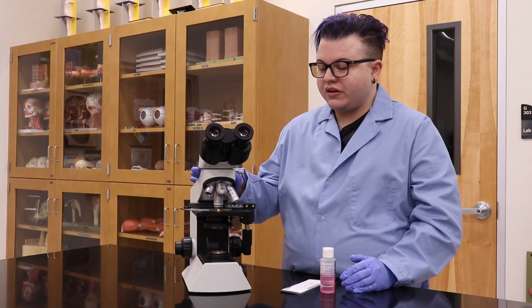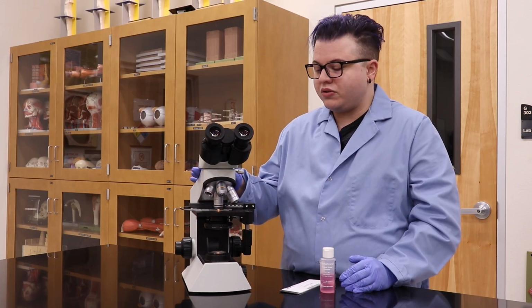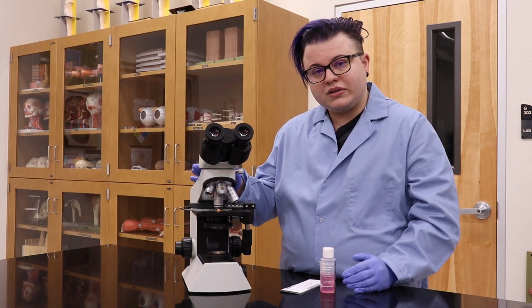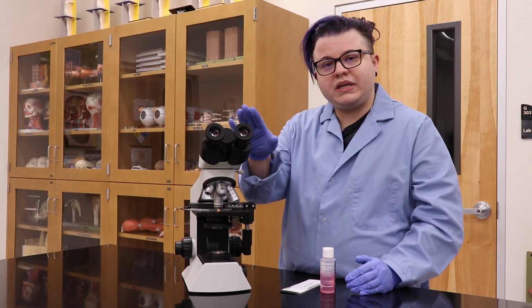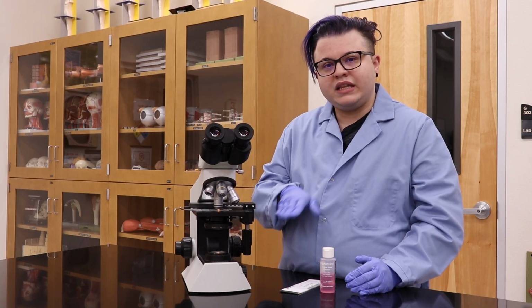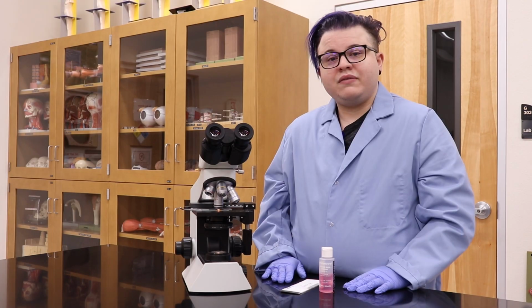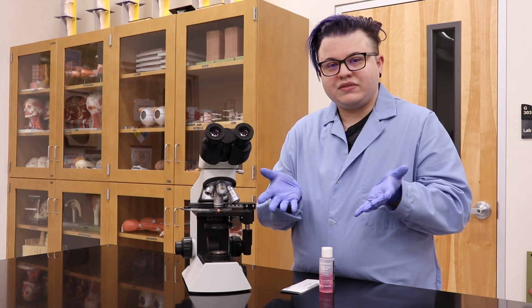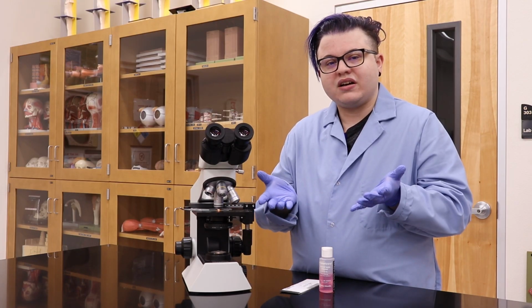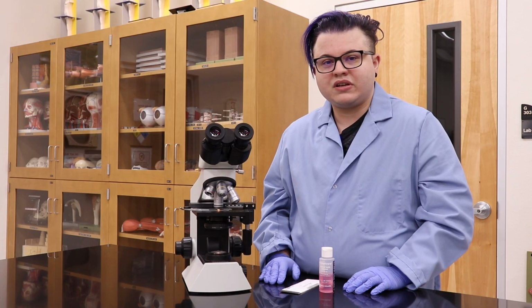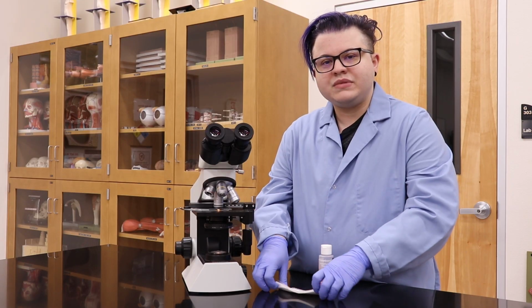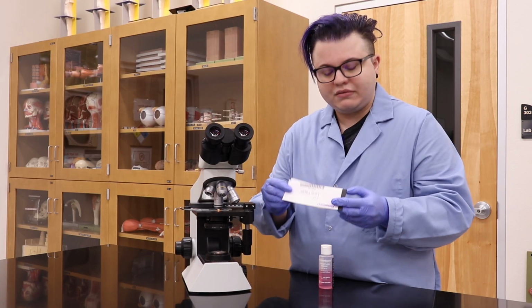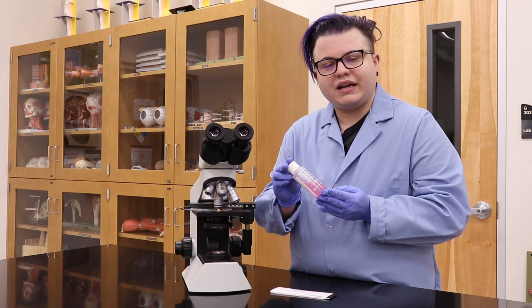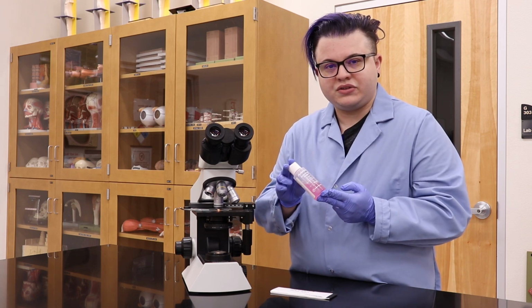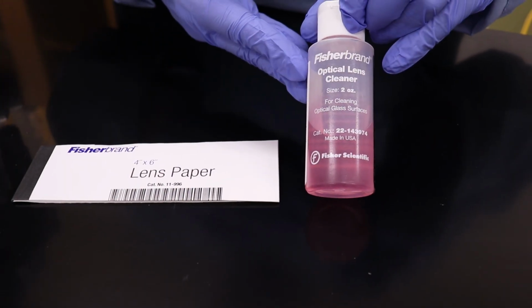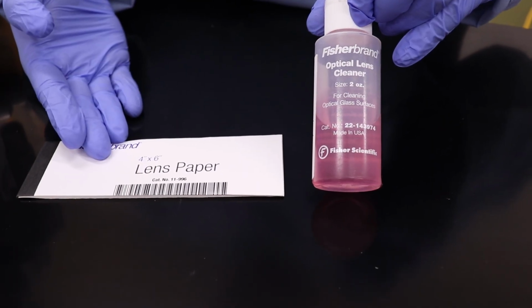This microscope is currently set to 100x with immersion oil on a prepared slide. We will start out by cleaning the eyepieces, then the objectives, and then the prepared slide itself. If you haven't already, put on some gloves to make sure that the oils from your hands aren't deposited on the microscope while you're cleaning it. The items that you'll need are some lens paper and maybe some microscope lens cleaning solution. This is the optical lens cleaner, and this is the lens paper.